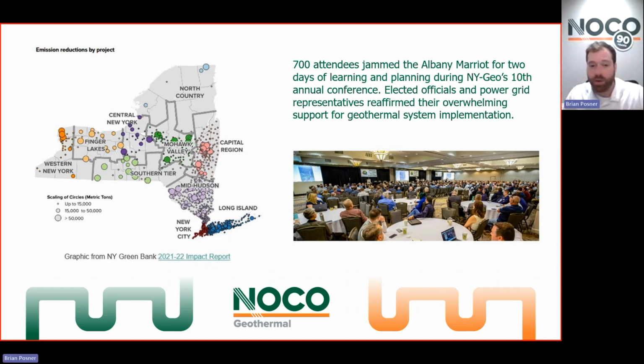With geothermal, there's no byproduct waste to exhaust. There's no combustion chamber to clean the byproducts of burning fuel out. It's actually a fairly maintenance-free system. So beyond the operational savings of using such a low amount of electricity to operate it, there's also those maintenance savings. So we're seeing property managers switch to geothermal, and these are guys whose business it is to know everything about their buildings. So if New York City is any indication, this is the revolution that's coming.